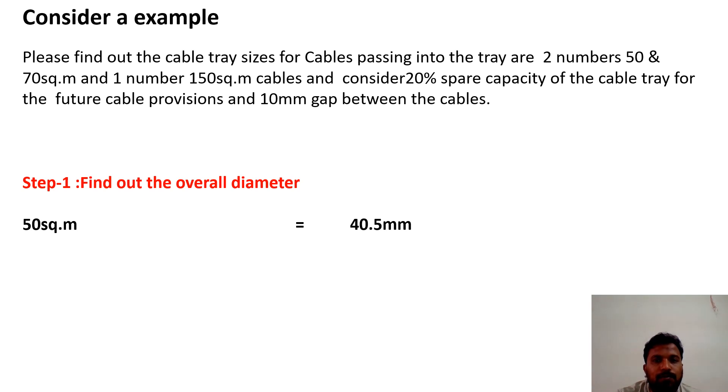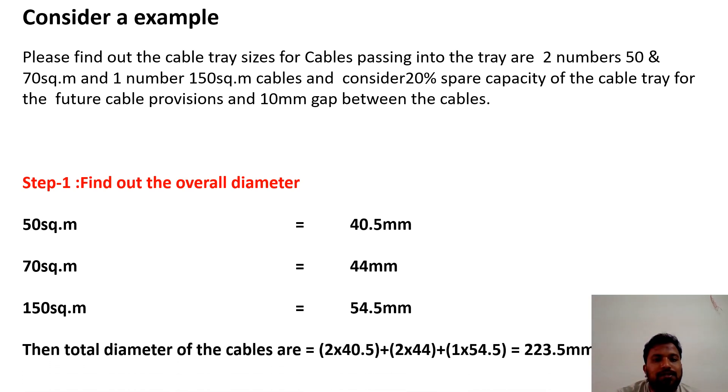These values vary from the manufacturers like Ducab, National Cables, Oman Cables, Riyadh Cables. Different types of cables are manufactured with different diameters. Which cables you are choosing? Select the same cable manufacturing chart and take the values from that one. 50 square mm is 40.5mm, 70 square mm is 44mm, and 150 square mm is 54.5mm.